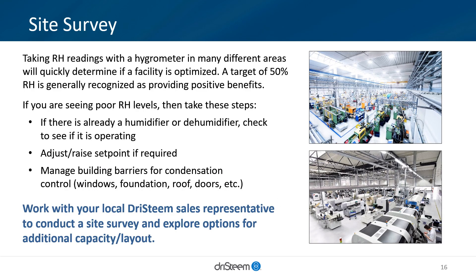Taking RH readings with a hygrometer in various areas will quickly determine if a facility is optimized. A target of 50% RH is generally recognized as providing positive health benefits. If you see RH levels that are too high or too low, then take these steps: first, if there is already a humidifier or dehumidifier, check to see if it is still operating. Next, raise or lower the RH set point as needed. Finally, manage the building barriers for condensation control. Work with the local DriSteem representative to conduct a site survey and explore options for additional capacity and layout.